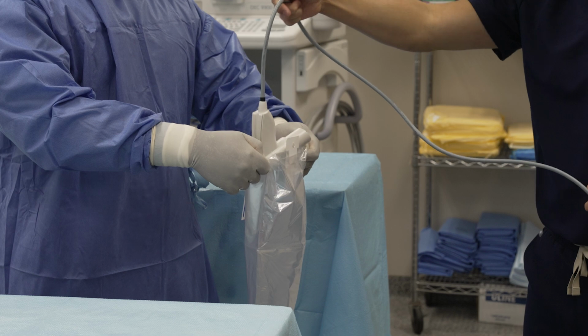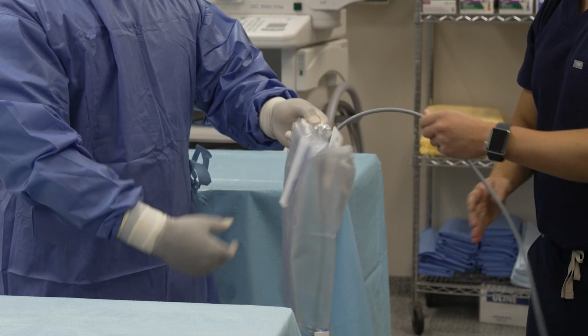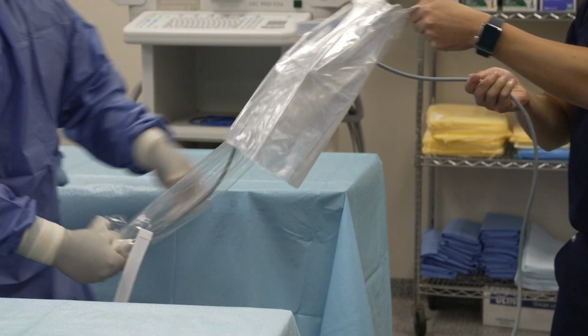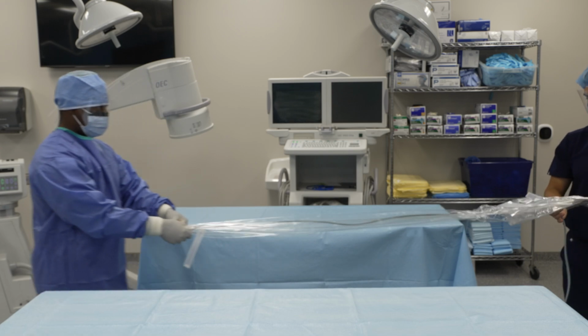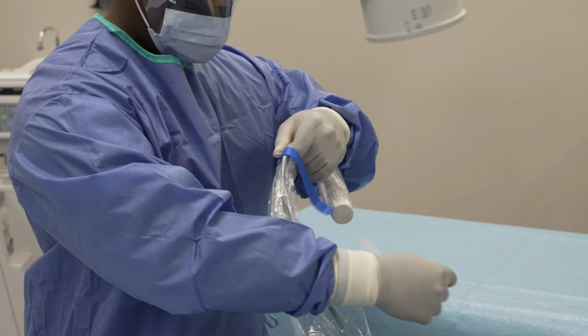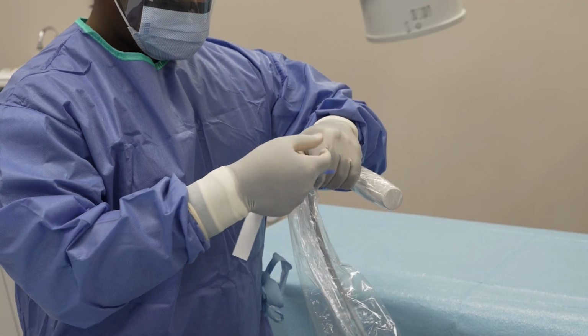Step 2. Drape motor and drive system. Using sterile technique, cover the motor with the sterile drape. Pull the drape over the whole length of the cable. Tighten the drape over the motor housing and wrap adhesive tape around the draped cable.